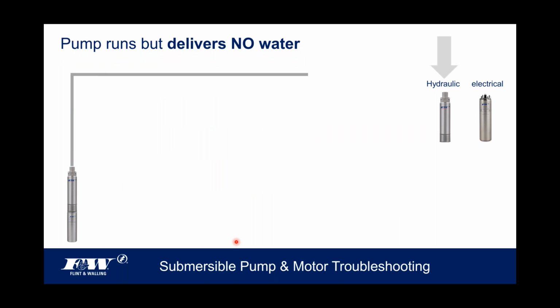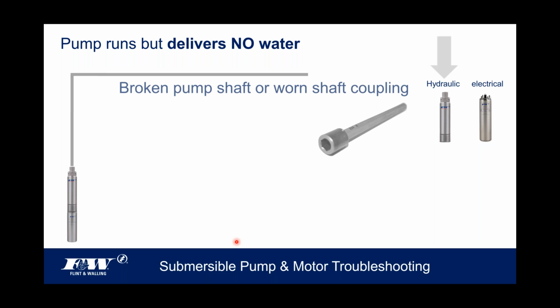Pump runs but delivers no water. Now, there's a big difference between no water and little water, right? But this pump isn't delivering any water at all. One possible cause is the pump shaft. You remember we had that pump shaft up here. If that is broken, your motor's going to run, but your pump's not going to turn, so the pump's not going to deliver any water. If this shaft coupling is worn out, you could again have a situation where the motor's running, but the spline on the top of the motor is just spinning on the inside of that shaft coupling. So it's not turning the pump. That might be a situation.